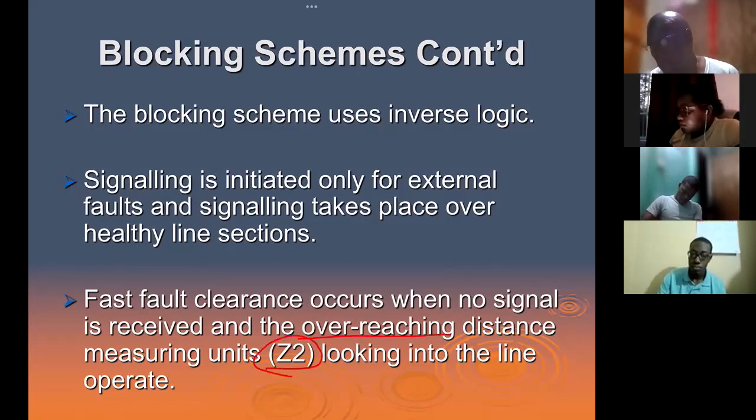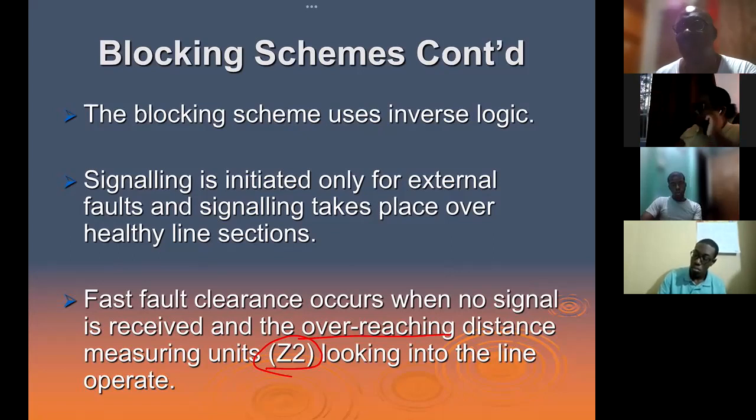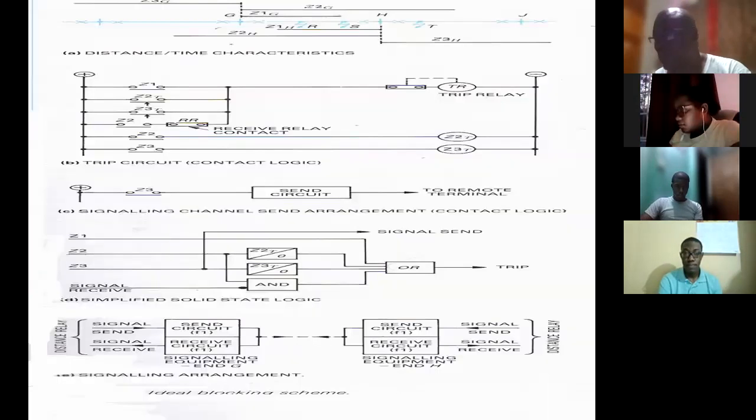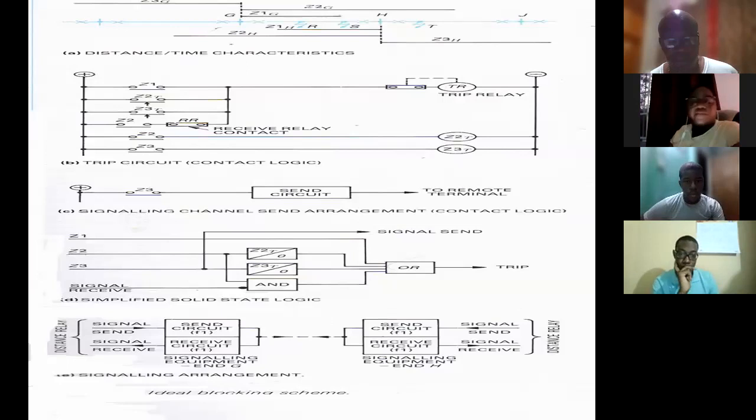And we want these now to operate instantaneously. So if we receive a signal, it means don't operate. If we don't receive, it means please go ahead, operate. So let's go through the logic circuit. All right, first things first.